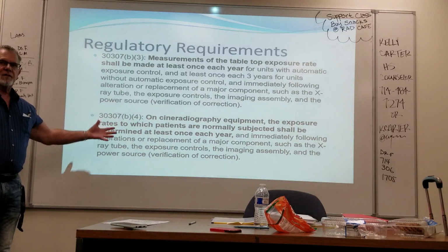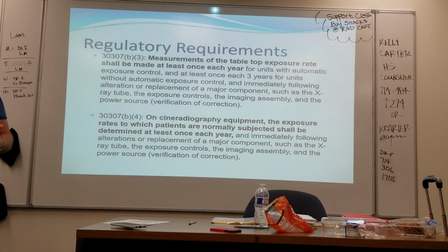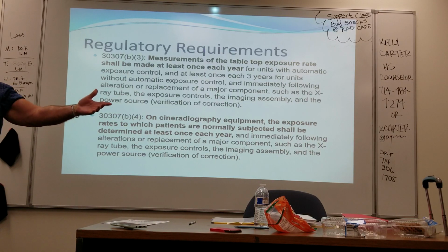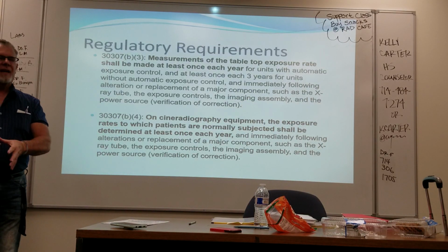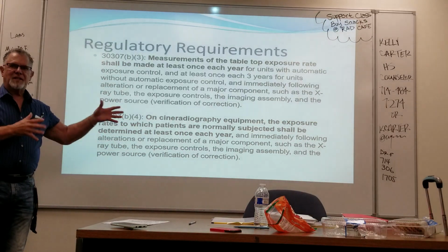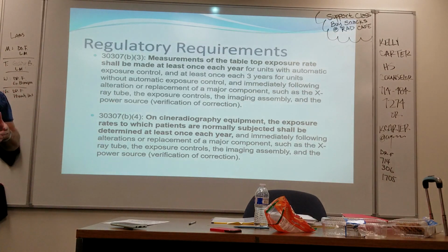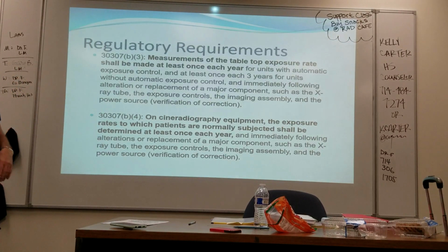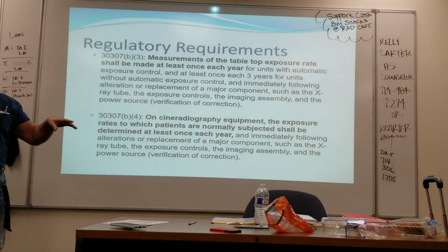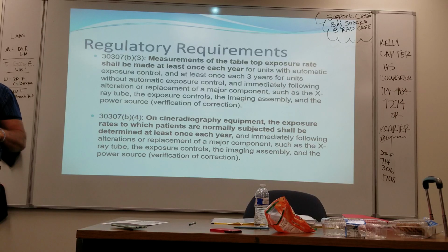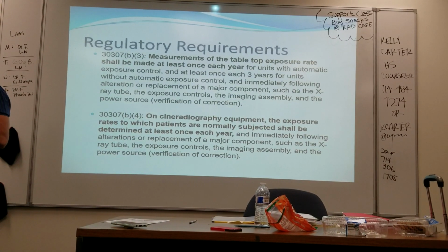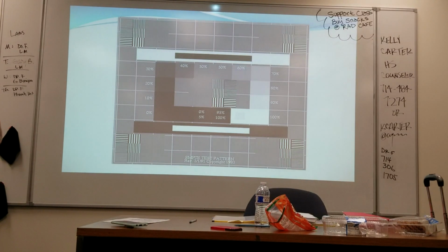When we moved to digital, there were arguments with the state. They said, well, you're using pulses, so anything over 15 pulses. And it's like they had to understand the difference between pulsed exposure and angiographic exposure, where you're actually doing frames, not pulses. It took a long time, but they finally agreed 15 frames per second or above is considered Cine. So if your equipment is capable of doing that, then you also have to measure tabletop exposure at those rates. SMPTE.